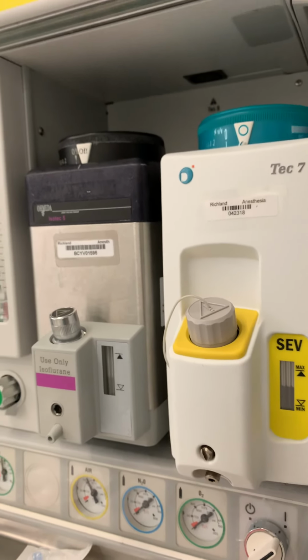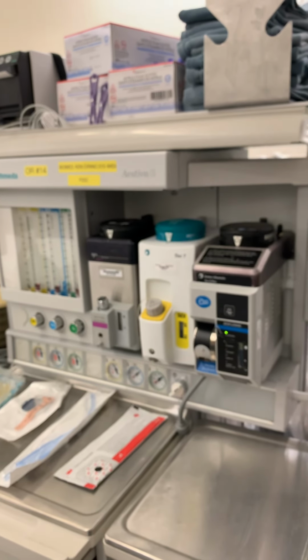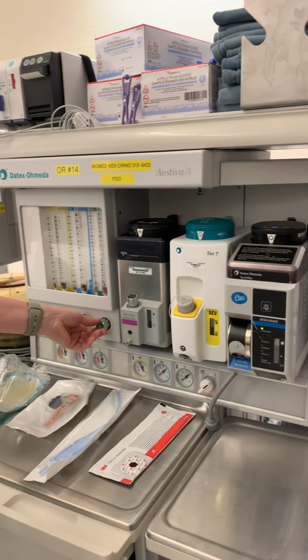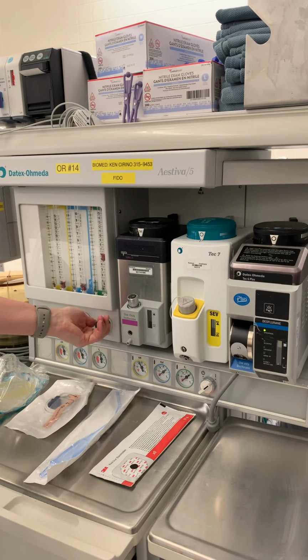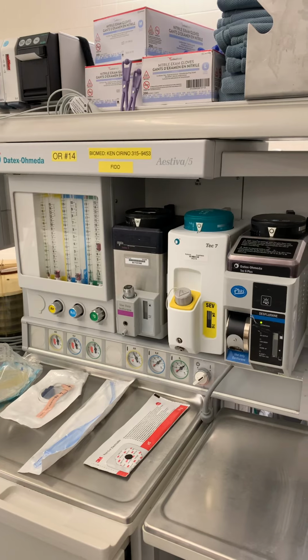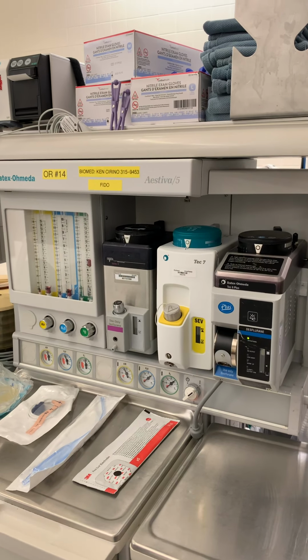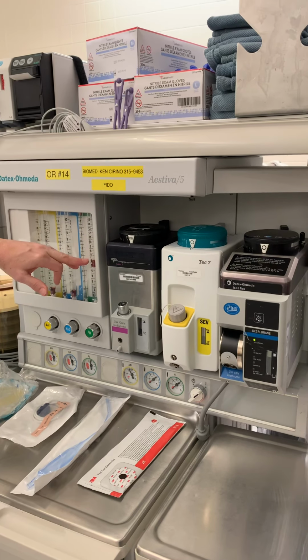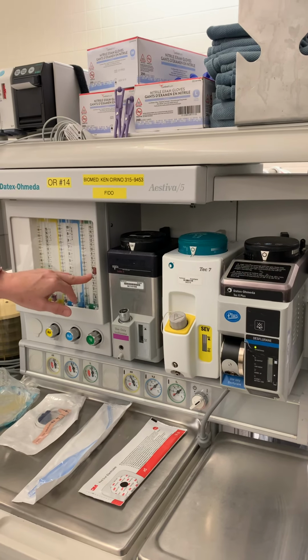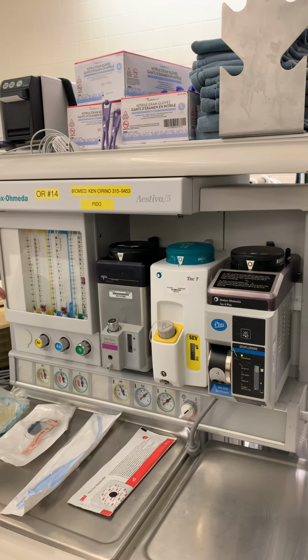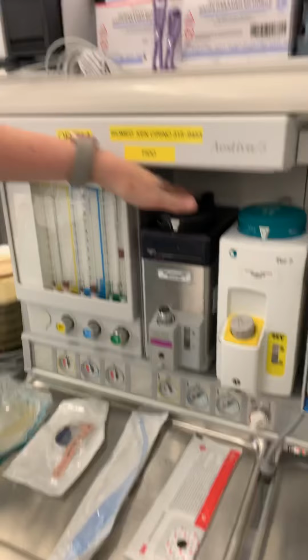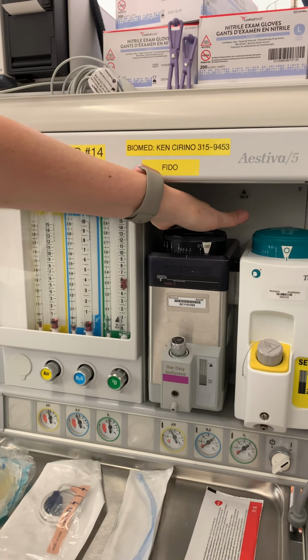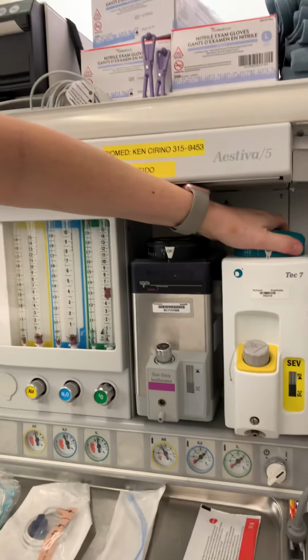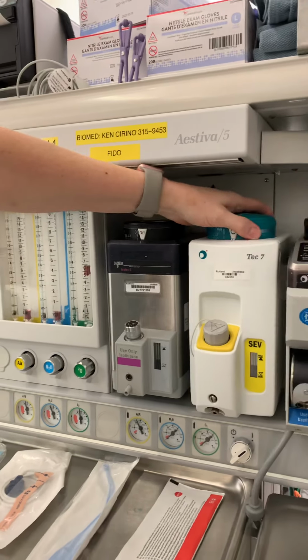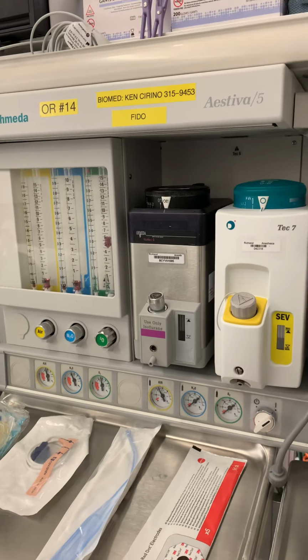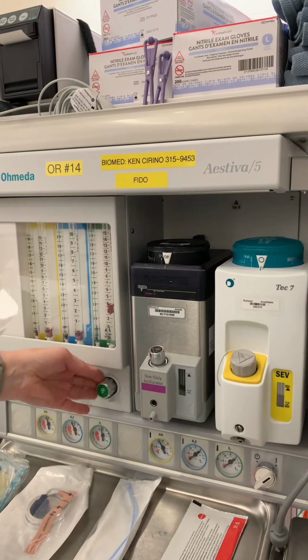So moving on to 5, you want to check the vaporizer back pressure. The instructions are to set your O2 flow meter to 6 liters. So we're going to turn till we achieve 6 liters of oxygen, and then we're going to turn on each vaporizer one at a time. You don't want this flow bobbin to dip below 5 liters, or move at all would be nice. So testing it, we're going to turn on the ISO, and if you notice, it barely moved. And we're going to turn on SEVO, and again, it barely moved. So it passed that test, and then we are done with that test.